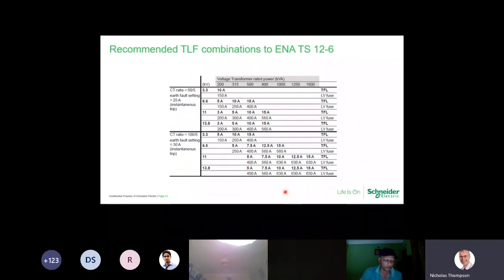Chart for selecting the appropriate TLF fuse for a given transformer size. You'll notice there we've got the CT ratio as a choice. On some of them you've got the choice, and others you don't have a choice. And the maximum fuse we can fit on time limit fuse protection is 15 amps. This is something that the ENA, the Energy Networks Association, have actually agreed amongst themselves, and is very much in use with the DNOs and with private networks as well. It is a recommendation. The final choice is going to be down to the consultant or protection engineer to determine the right size fuse, but you are limited on the number of fuses available.